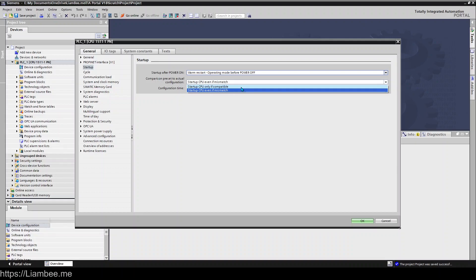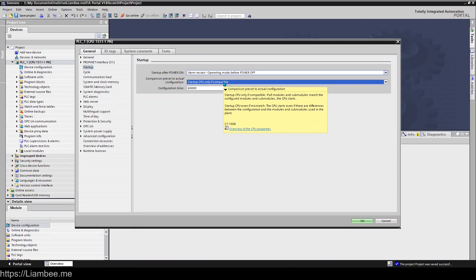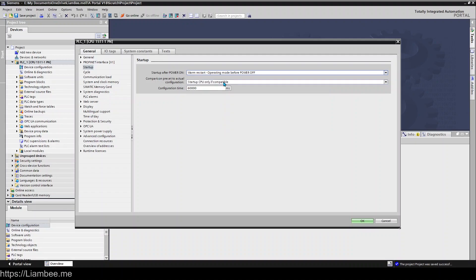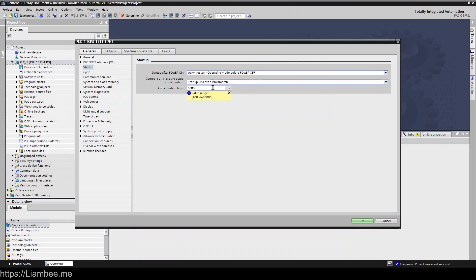So I think particular firmwares and stuff of the IO modules wouldn't trigger it saying it was incompatible unless there was a major difference in how it operated. But if you have startup only if compatible selected and someone puts a different type of 16-way input card in or 8-way output card or whatever they've changed and it's not compatible by Siemens standards you won't be able to start your CPU even if you would be able to logically operate stuff the same way. So just be careful with this one if you don't really know what you're doing it's best to just leave it as startup CPU even if there's a mismatch. You'll get a warning on your compiler that the output cards aren't the same or it's running in a mismatched state and I think you get the maintenance light on as well.